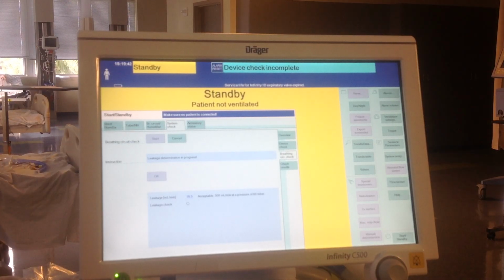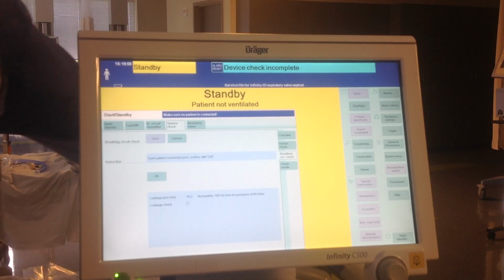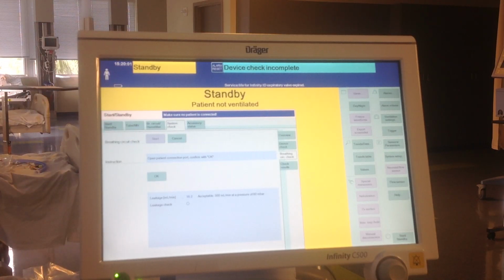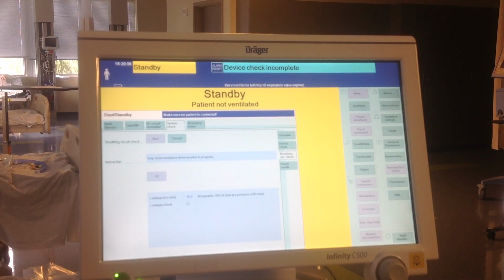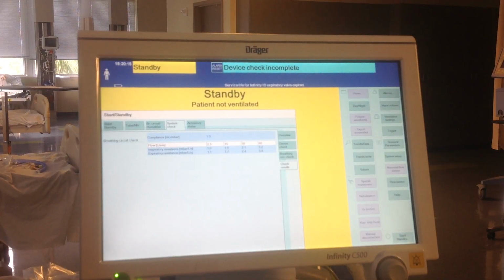This can leak up to 300 milliliters per minute at a pressure of 60 millibars. Just remember that it has a preset leak and it's going to measure everything for you. Open patient port connector, connection port, hit OK. It was checking the resistance, breathing circuit check finished, and we are done. I wanted to show you also check results.